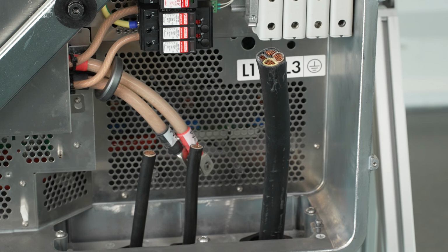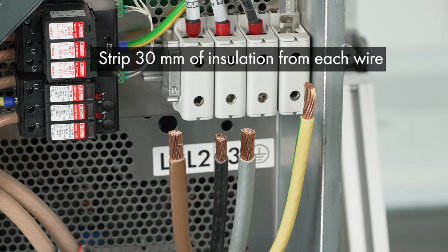Before we begin connecting the AC conductors, we first check the technical requirements of the system. Depending on the configuration, a suitable medium voltage transformer is required for this. Next, we prepare the cables according to the specifications.